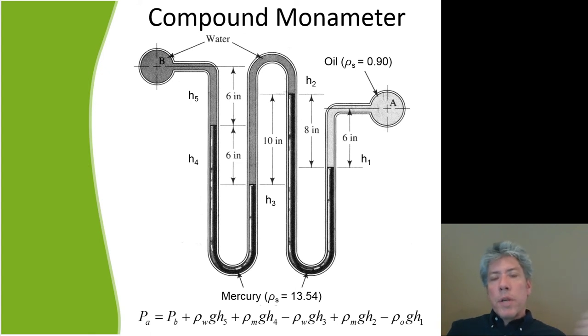Rather, what I did was I simply used a length of tubing that was clear, put some water in it, and voila, I had a manometer. I could connect one end to a port on the duct work in one area that I've added to the duct work, and the other to a port in another section of the duct work. And just by measuring the deflection of the water once the fan was on, I could actually calculate the pressure difference between those two points. So this is something worth knowing. It's interesting, it's useful in many situations. There are still manometers in industry. Not all industries have completely gotten away from them. Sometimes they're just very reliable mechanical means for measuring pressure differences.